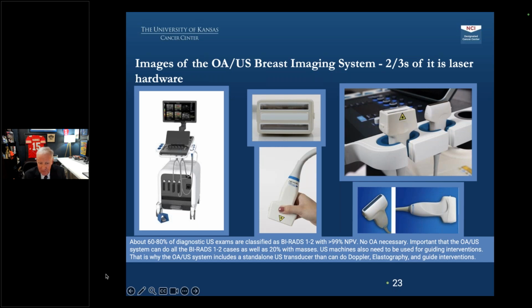It's important to point out that the Imago machine also has a regular standalone 5 to 18 megahertz transducer. This is important because the majority of breast ultrasound cases, probably 80% or so, can be imaged with the standard probe as they are assessed as a BI-RADS 1 or 2. It's only in a minority of cases in which a suspicious mass is detected that one would need to proceed to image the mass with the Imago probe.